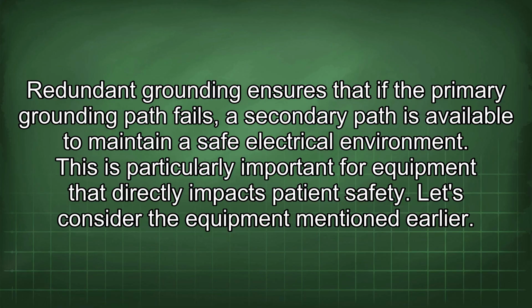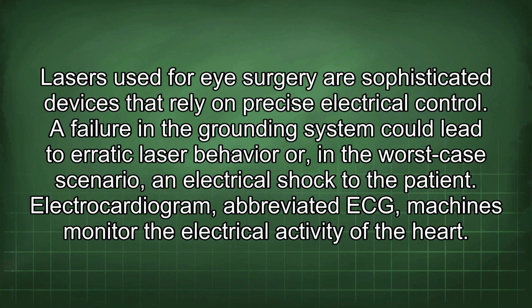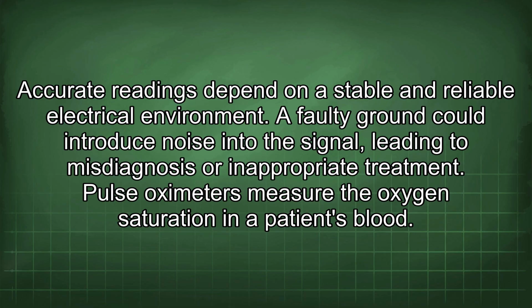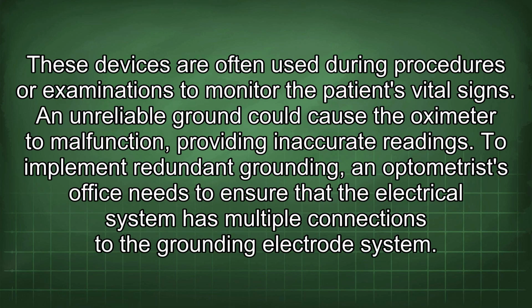Let's consider the equipment mentioned earlier. Lasers used for eye surgery are sophisticated devices that rely on precise electrical control. A failure in the grounding system could lead to erratic laser behavior or, in the worst-case scenario, an electrical shock to the patient. Electrocardiogram, abbreviated ECG, machines monitor the electrical activity of the heart. Accurate readings depend on a stable and reliable electrical environment. A faulty ground could introduce noise into the signal, leading to misdiagnosis or inappropriate treatment. Pulse oximeters measure the oxygen saturation in a patient's blood. These devices are often used during procedures or examinations to monitor the patient's vital signs. An unreliable ground could cause the oximeter to malfunction, providing inaccurate readings.